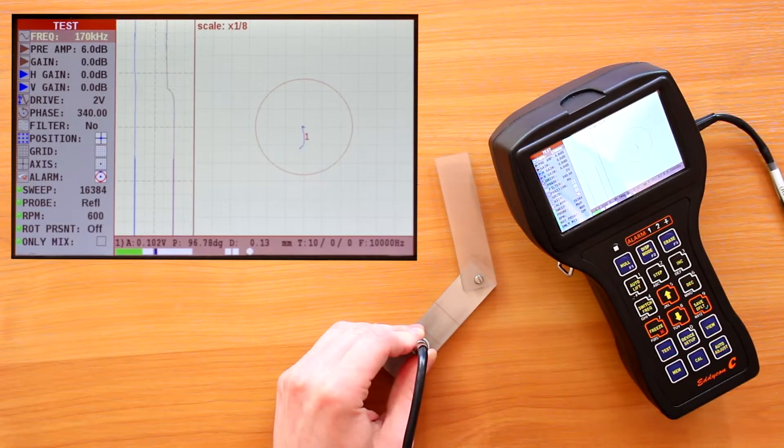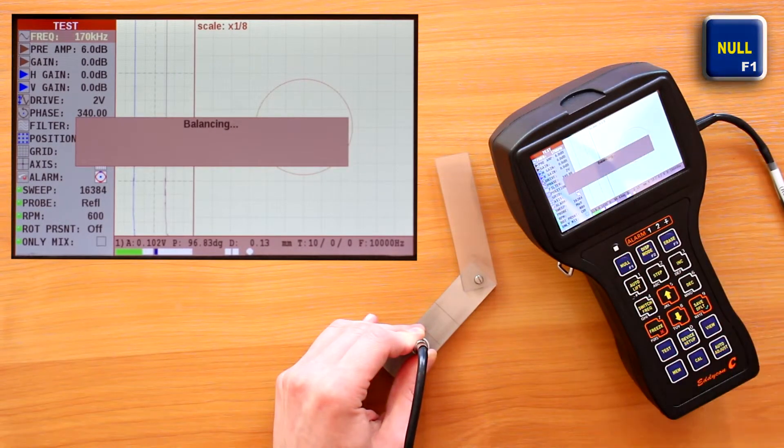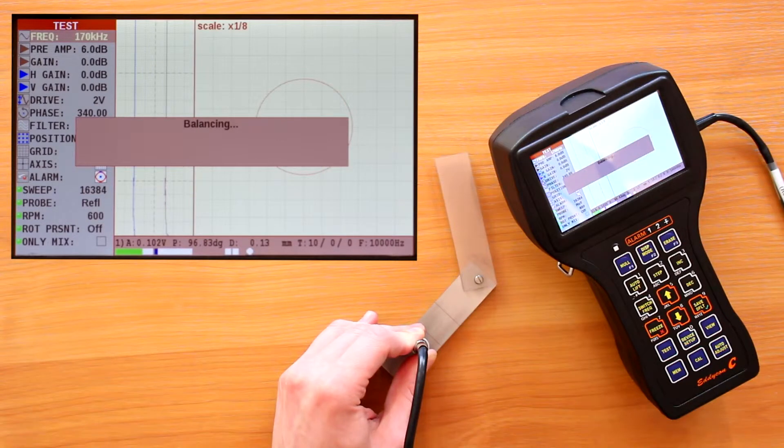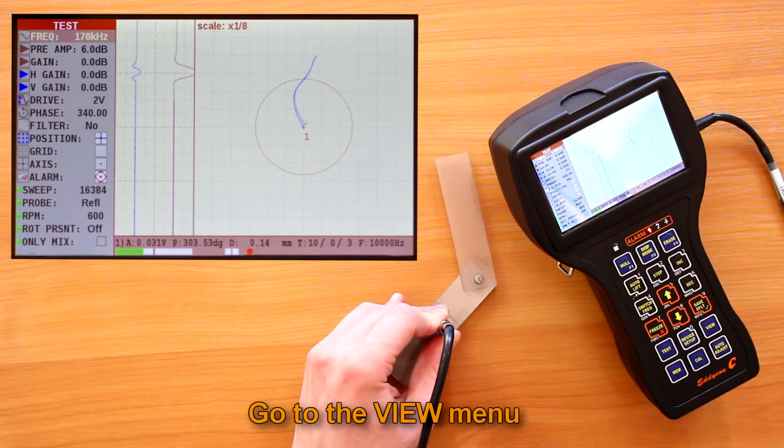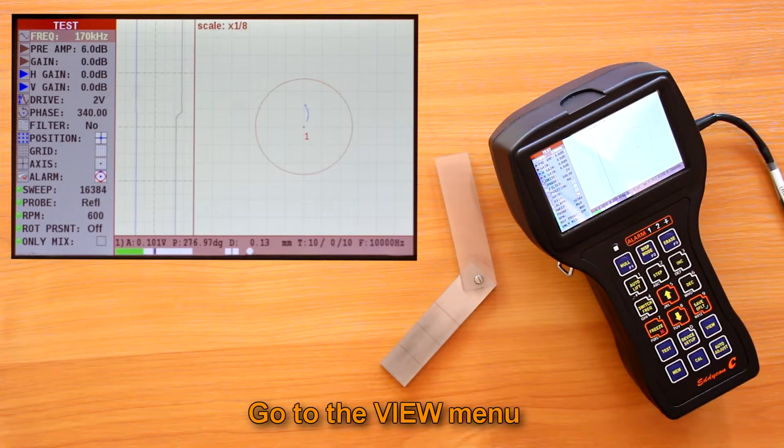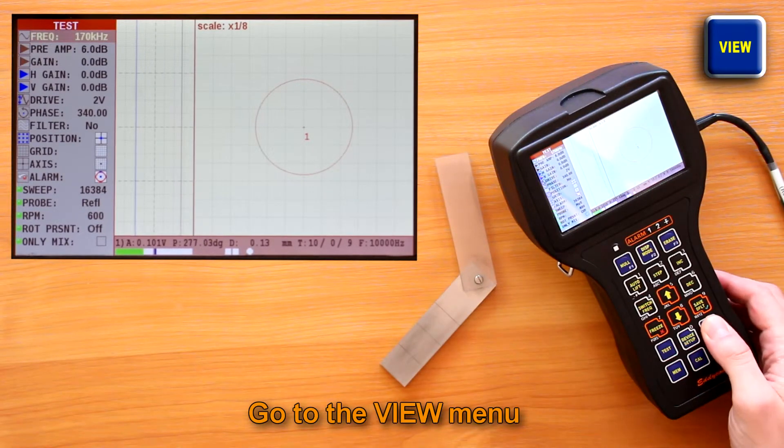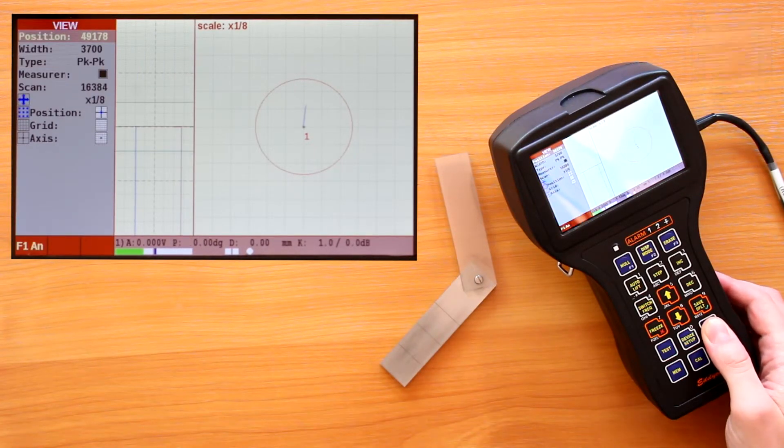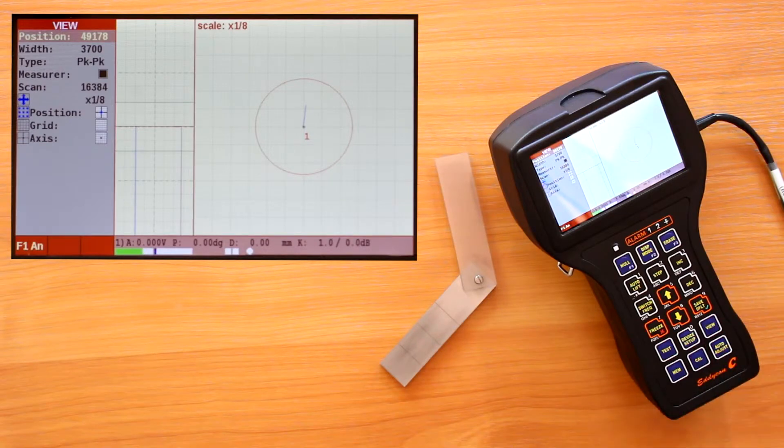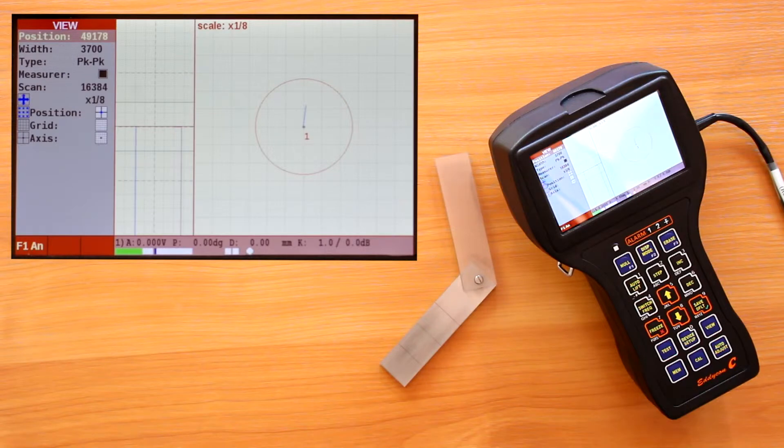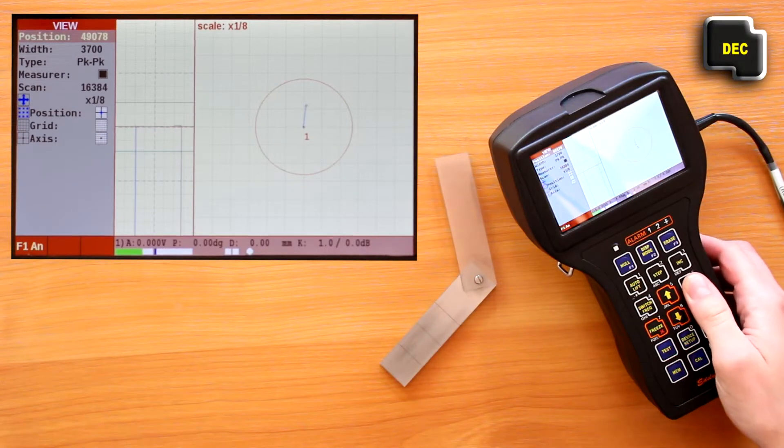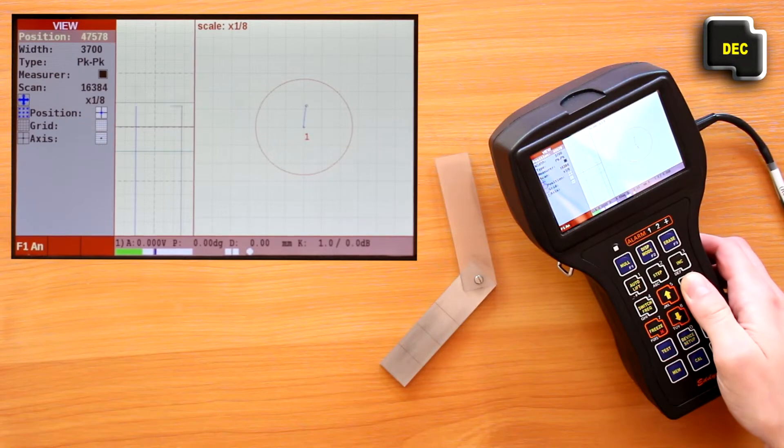Pass the defect with an appropriate scan speed. After that, go to the view menu by pressing the view key. When entering this menu, an operator is offered to view and analyze both current and saved test results. Parameters position, width, and cursor type are the same as in calibration menu.